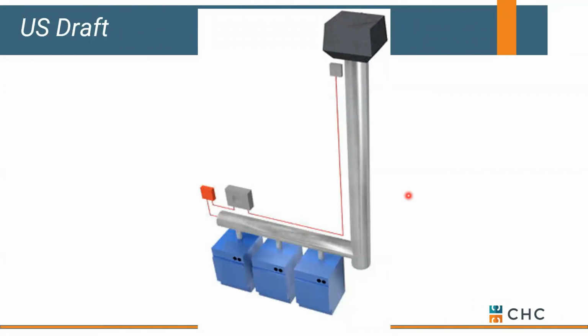Talking about venting boilers. There's times when you don't have an easy way to get those products of combustion out of your mechanical room. And sometimes you have to use a mechanical draft system. This is simply a fan up here that's controlled by a VFD, and it reacts to the pressure in the stack. We deal with US Draft. They are excellent at designing systems.